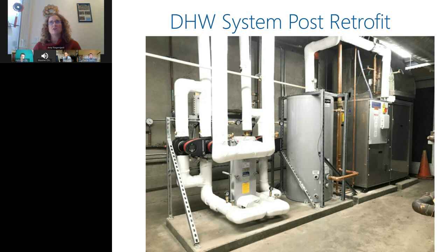When this was installed in January and we turned it on and were commissioning it, the challenge was that people living right above this boiler room found it loud. If you can see in the corner there, there's a huge plenum where we're exhausting the ducting off the cold air, and that's causing reverberations on dampers and a lot of noise. So right now we're retrofitting the heat pump and putting on larger fans to work on that.